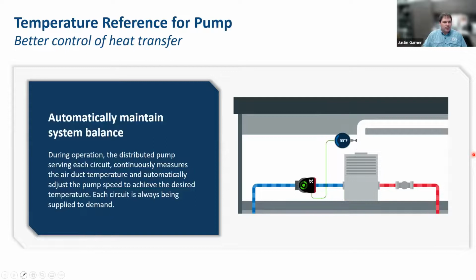And as much as we'd like to think that we can just put things in the systems and flip the switch to on and it would work, oftentimes that's not the case. So from a balancer's perspective, the main role with this system is to, number one, verify that we're getting design flow through the coil, and also to verify some of those parameters that Pete just talked about. The flow limit might not get set up correctly. There could be other parameters that may not get loaded correctly.